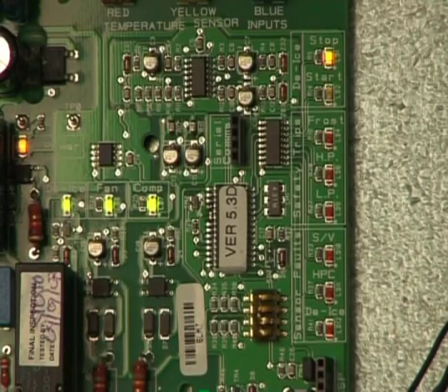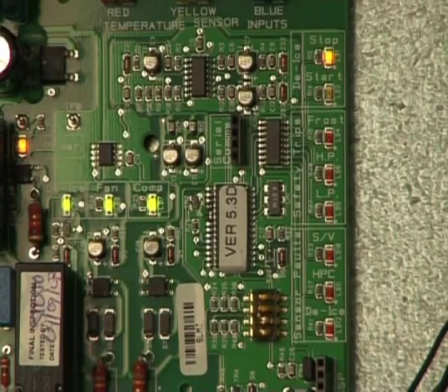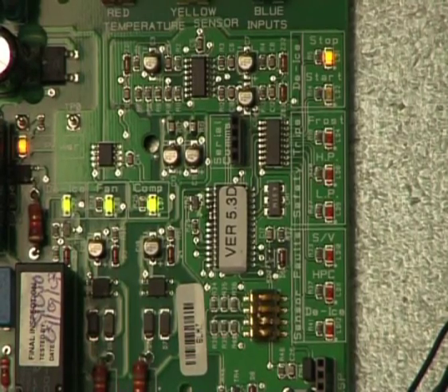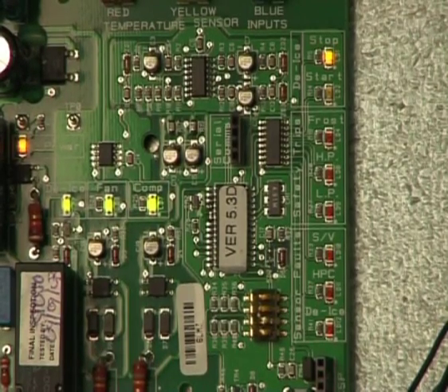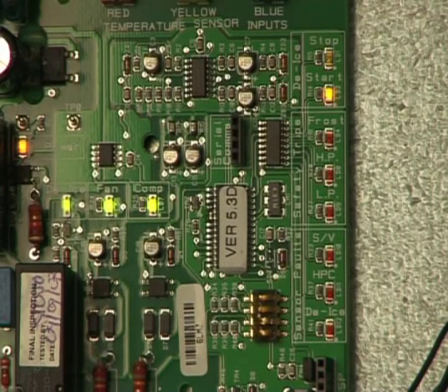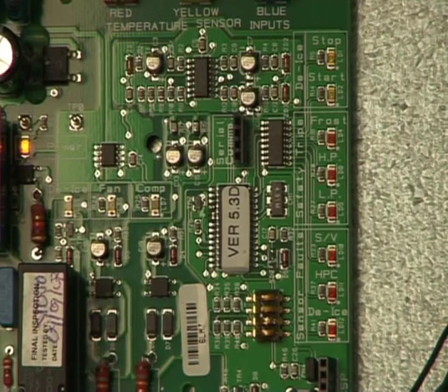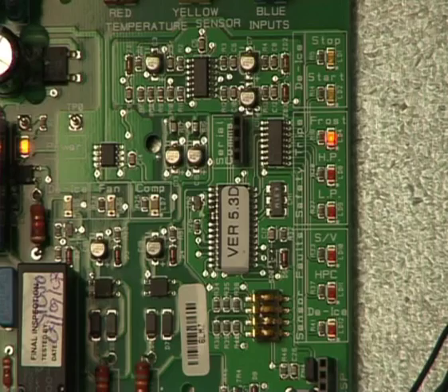The DI stop LED indicates outdoor coil temperature at or above 12 degrees C. The stop LED is always illuminated whenever the outdoor coil temperature is above 12 degrees. This is whether the unit's compressor is running or not. The DI start LED indicates outdoor coil temperature is at or below -4 degrees C. If neither start nor stop LEDs are illuminated, condenser coil temperature must be between -4 and +12 degrees C. The frost LED indicates service valve suction temperature is at or below -10 degrees C on the cooling cycle.